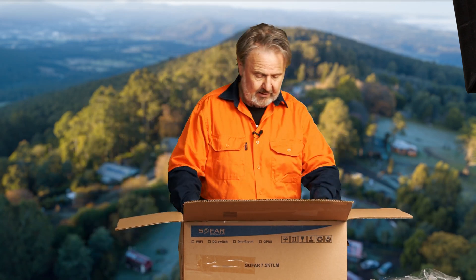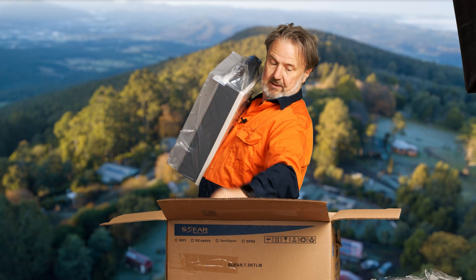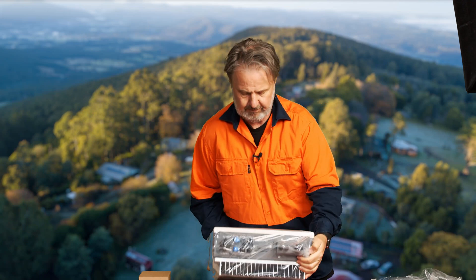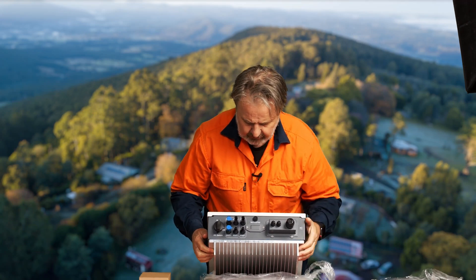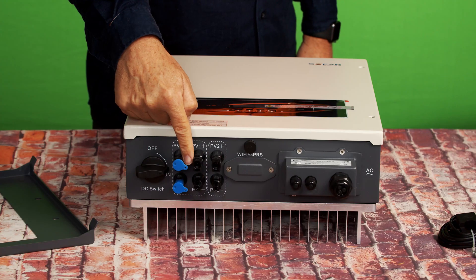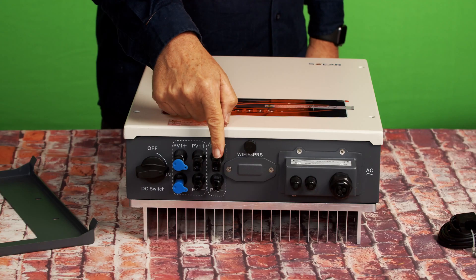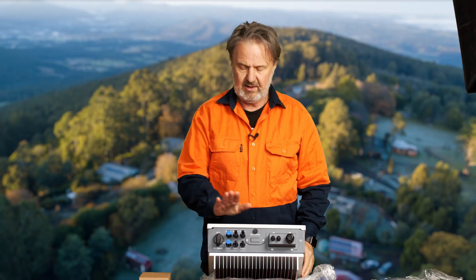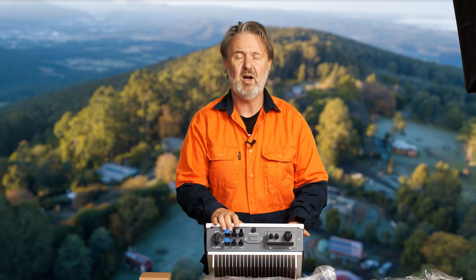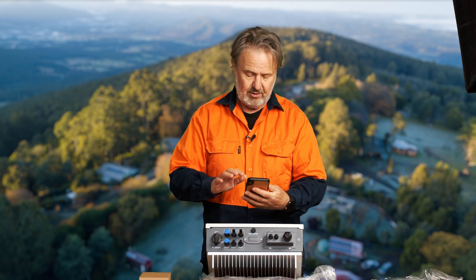Now let's actually have a look at the inverter itself — I haven't really done this one before so let's see what's in the box. We've got three inputs: there's PV1, which has one MPPT with two sets of inputs, and PV2. The reason for this is that the MPPTs on these are not symmetrical — one is the primary and one is the secondary, and one can take a much higher current maximum than the other.